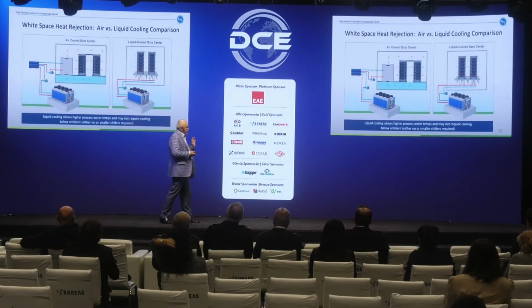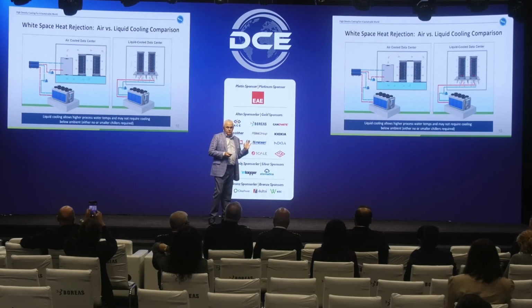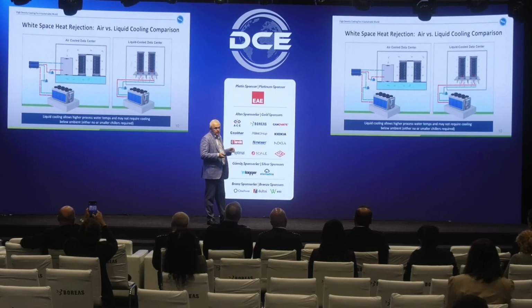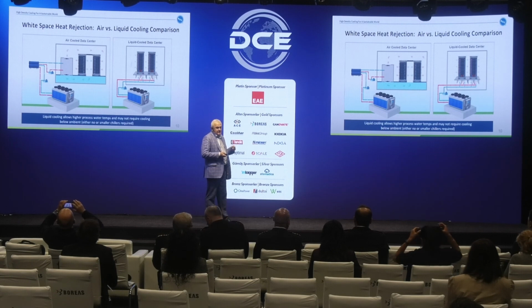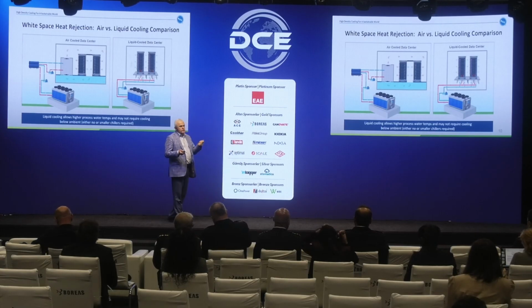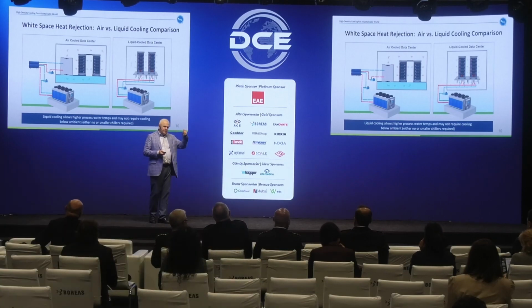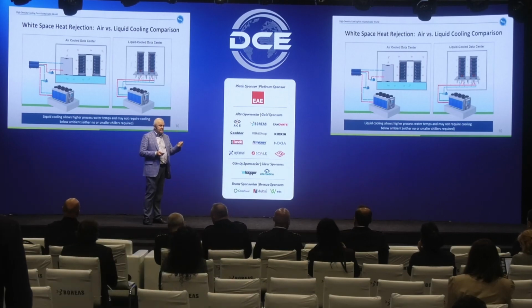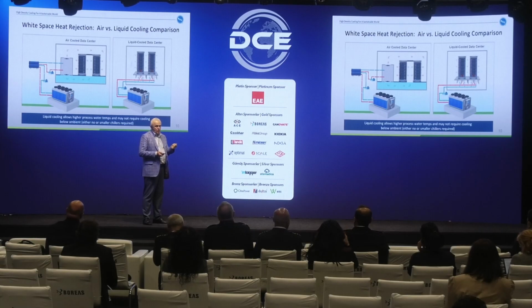So right now, on the left side, we have an air-cooled data center, which needs a chiller. You cannot get rid of the chiller. And the problem with the chiller, let's face it, is that it's very economical, the price per ton is very good. But the purpose of this building is data computing, data storage. You are not in the business of cooling. So keeping electrical power for cooling just in case, in the middle of the summer, you have very hot days, is a waste. You want to free electrical power from the chiller to use for your core business, which is IT storage, IT computing, and so on.